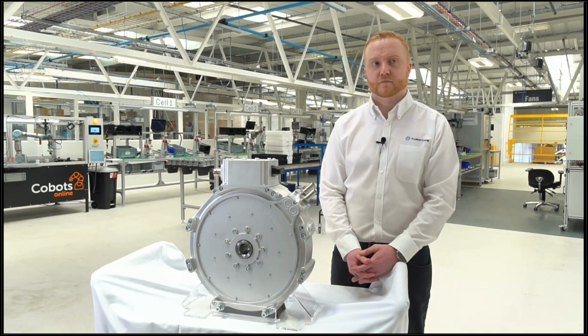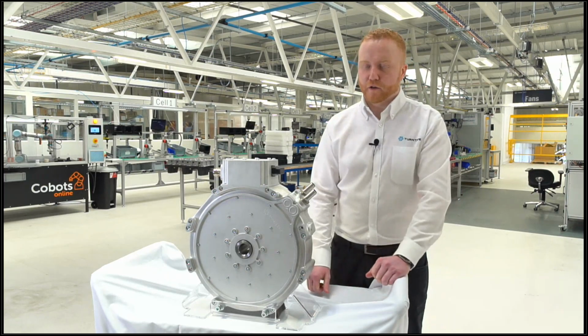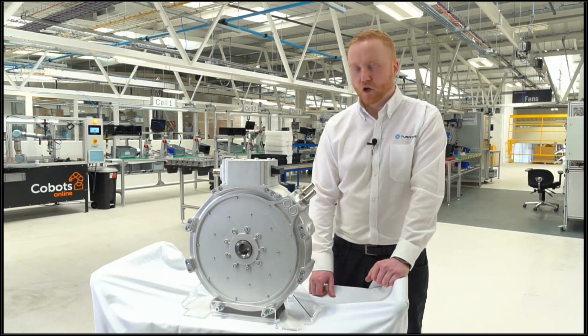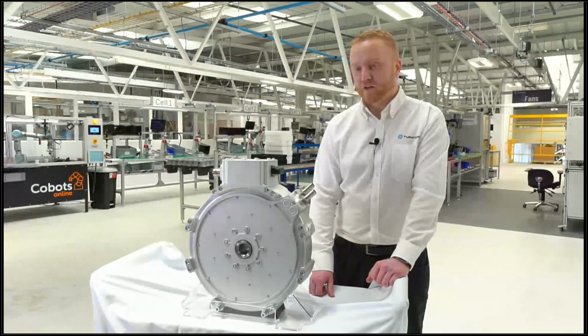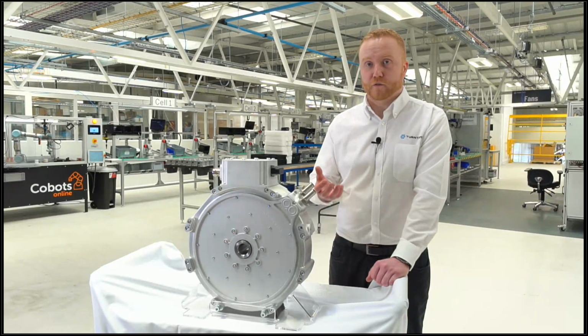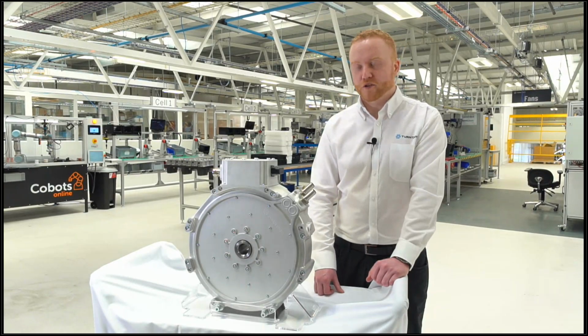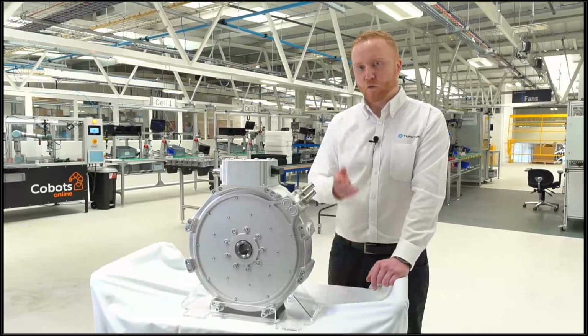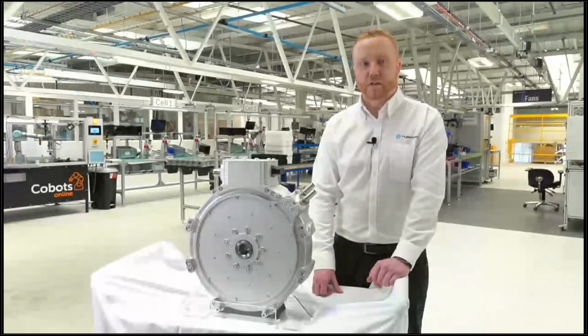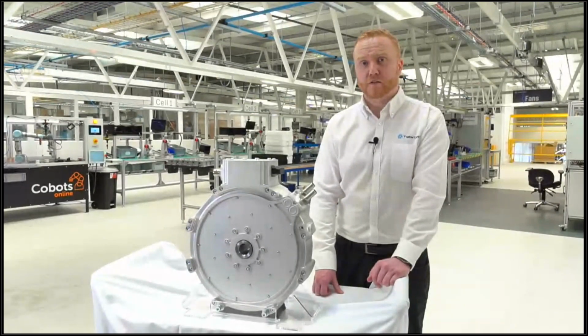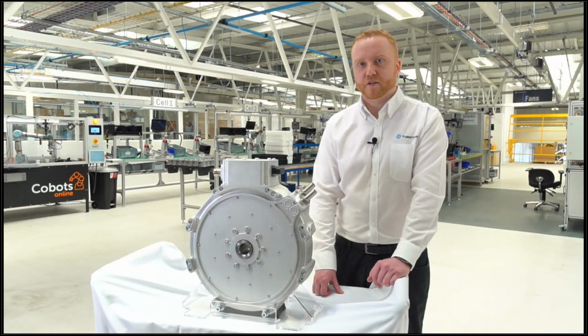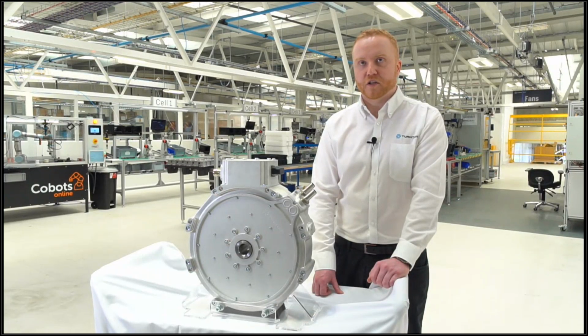How much cooling is required, and can you talk about that a bit more? The nominal value off the top of my head is 8 liters a minute. Any lower than this flow rate and you'll see an increase in temperature for the amount of coolant, as well as potential thermal effects that may reduce performance rating. Go higher than 8 liters a minute and there's not much benefit in performance—it's roughly a 1-over-x curve with diminishing returns at higher flow rate. We feel 8 liters a minute is a reasonably standard number compared to other electrification components like inverters and batteries. The pressure drop, which I don't have to hand, is reasonably low for the flow required, meaning you don't need a much larger pump to deliver the cooling requirements.